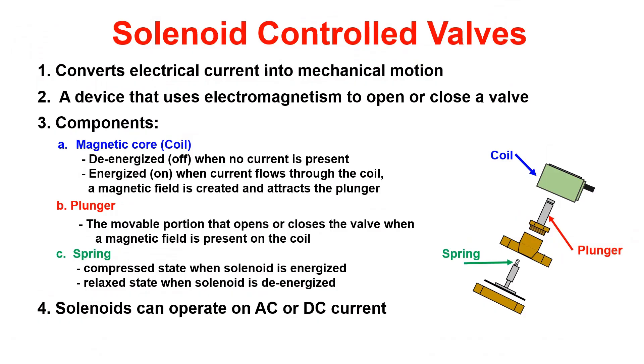Solenoid control valves are used to convert electrical current to mechanical motion. This device uses electromagnetism to open or close a valve. The valve is comprised of a magnetic core or coil, a plunger, and a spring. When an electric current is passed through the coil, a magnetic field is generated and the plunger is pulled in. When the current is removed, the solenoid is returned to its de-energized state by the spring.